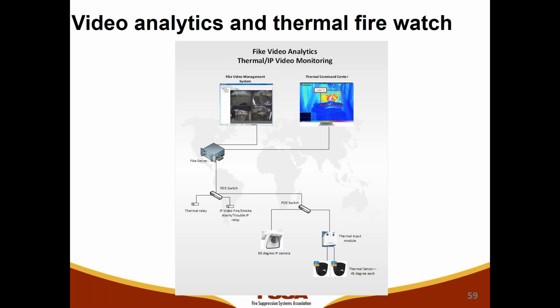So you have thermal imaging in areas where you have a lot of cable trays, cable spreading rooms, up above the switchgear racks where you have a lot of cable trays. It's very dark, difficult to locate detectors. Video analytics, the left camera there, that's a standard video camera. The video analytics can monitor that image for flame, smoke, reflected flame, motion, oil mist. So this can be used as a primary fire watch, or when personnel leave the site or the area and you're required to have 4 to 8 hours of fire watch after the work. This can be set up for monitoring in a central manned location.